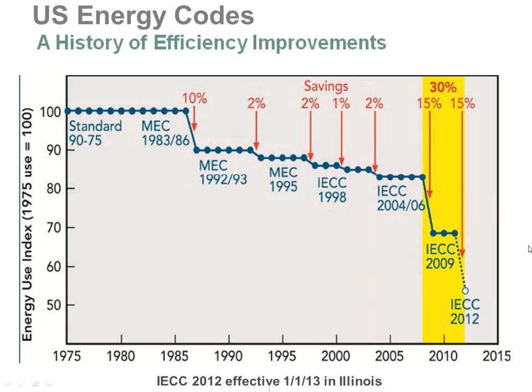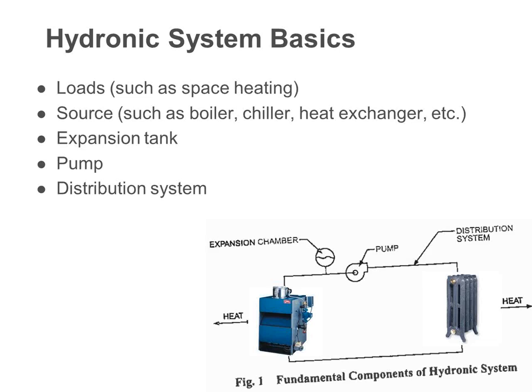Okay. The other component of the system is the expansion tank. This is something you really want to look for when you're down in that boiler room. Examine the system, see what they got going. The next component is the pump. This really should be called a circulator. Okay, we are not pumping water. We are circulating water. We're moving it around the system. We're not raising it like a well. Okay, so it should really be called a circulator, and that's what we're doing.